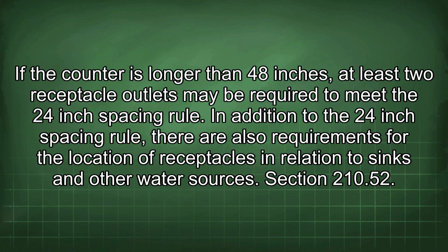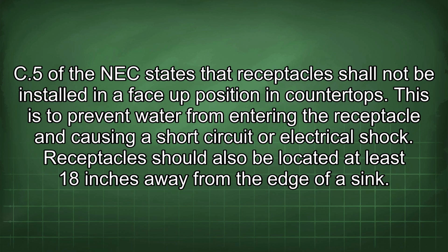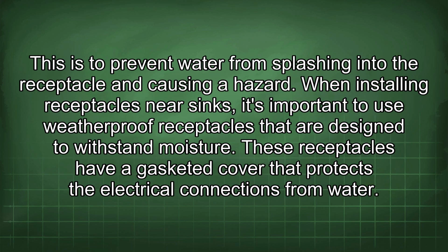Section 210.52 C5 of the NEC states that receptacles shall not be installed in a face-up position in countertops. This is to prevent water from entering the receptacle and causing a short circuit or electrical shock. Receptacles should also be located at least 18 inches away from the edge of a sink. This is to prevent water from splashing into the receptacle and causing a hazard. When installing receptacles near sinks, it's important to use weatherproof receptacles that are designed to withstand moisture. These receptacles have a gasketed cover that protects the electrical connections from water.